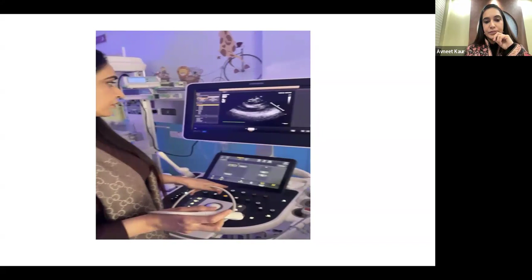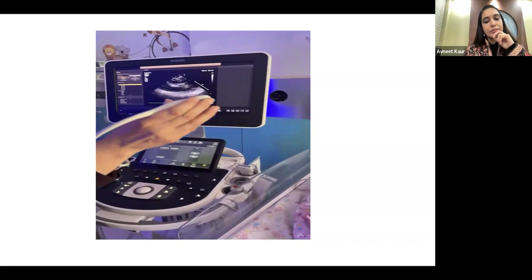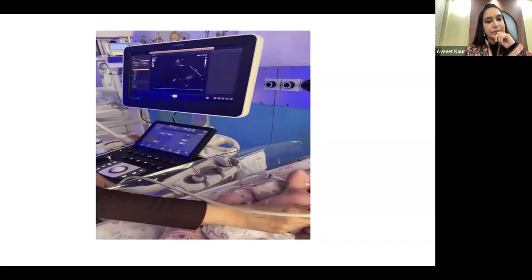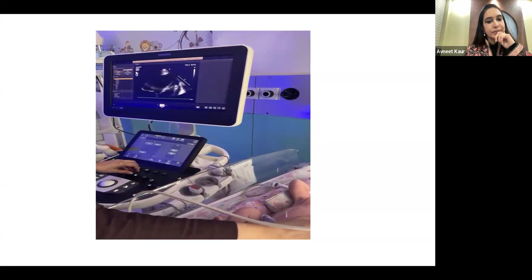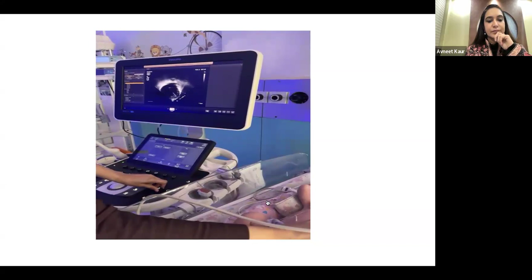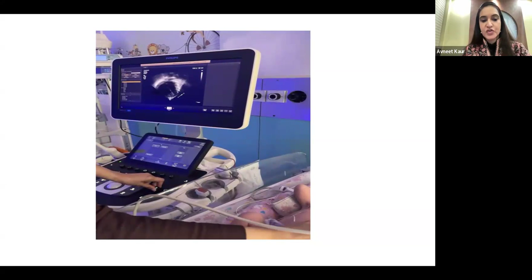So we pick up this B mode or the 2D mode, and when we put it on the baby, the 2D mode. So, and we adjust our image, as you can see here. Okay, now we are adjusting our image. We adjust the depth of our image. Okay, you can see here. We are trying to adjust the depth of image, and now once we have put this 2D mode, we have adjusted our image optimized. So I'll discuss about what is depth, how do we adjust the depth, but basically what I want to show is that this mode is the B mode or the 2D mode, which is like the black and white mode. And main thing is that how to get our image right or acquisition, which will be the other parameters, and we'll discuss about those a bit.